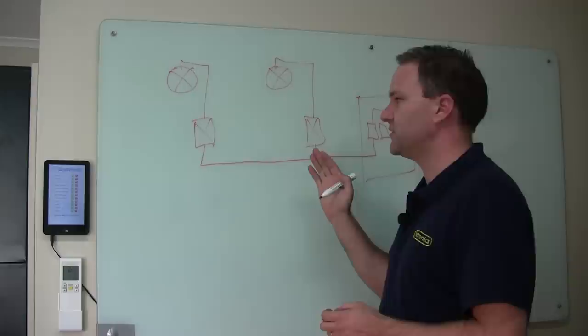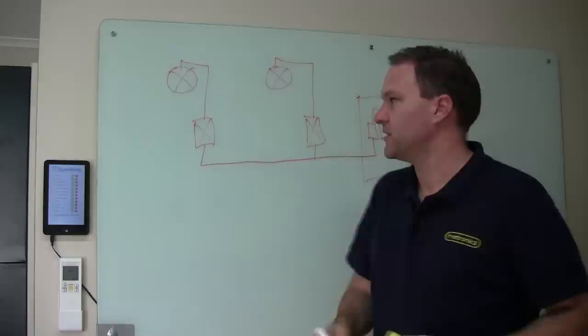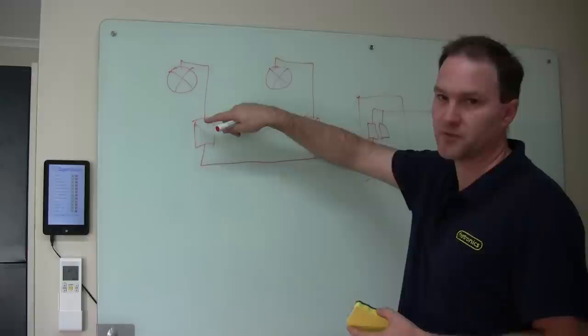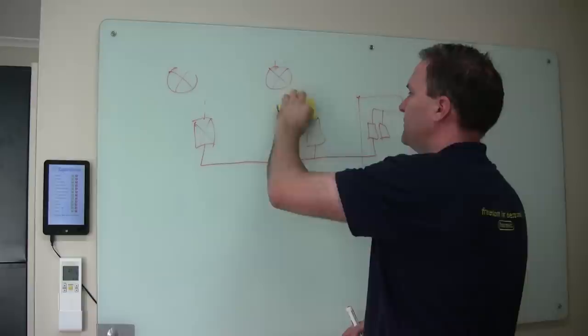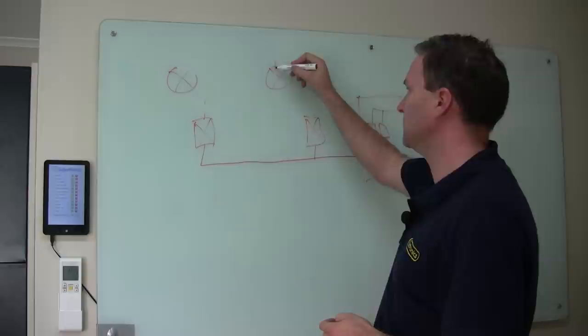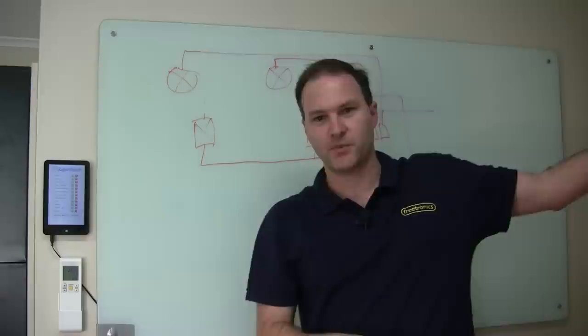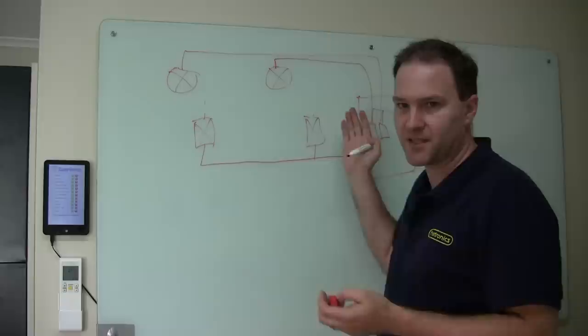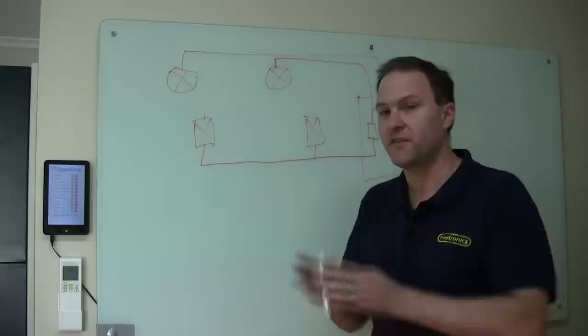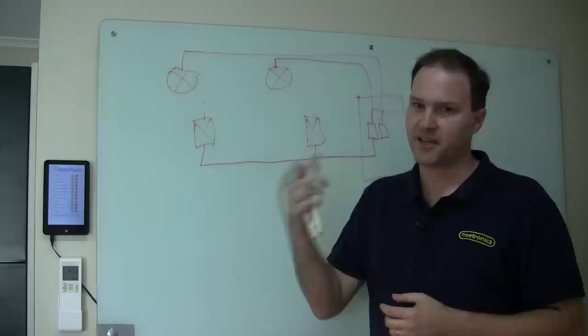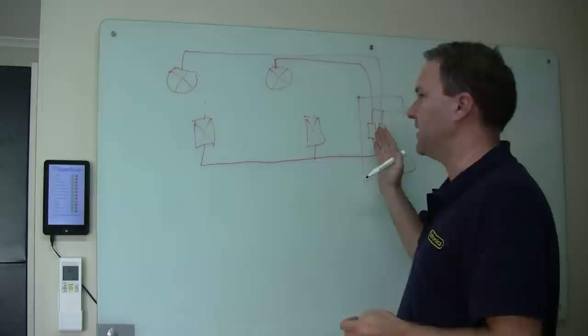So the approach that I'm taking is a little bit different. Instead of having all of these lights wired through local switches, what I've done is taken the opportunity of the renovations to remove all of the existing wiring and instead every light is wired all the way back to the switchboard. So in this room, for example, we've got lights up on the ceiling. The cable from that does not go to a switch on the wall. It goes all the way to the switchboard and is wired into its own circuit essentially. So we've got a whole bunch of circuits, one for every single light in the house. What that means is that instead of having just a couple of cables coming out of the switchboard, we've got a big fat bundle of cables because it's got to have a cable for every single load that you're going to control. The advantage that gives is that it means that everything is centralized and can be controlled from one point.